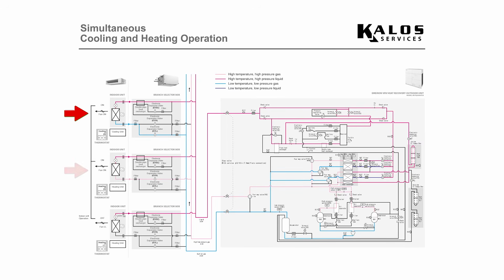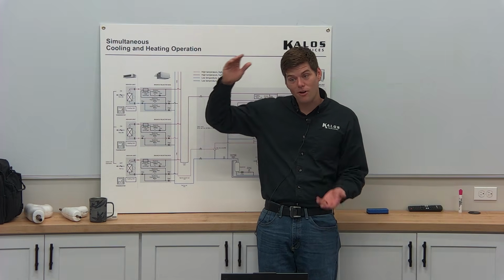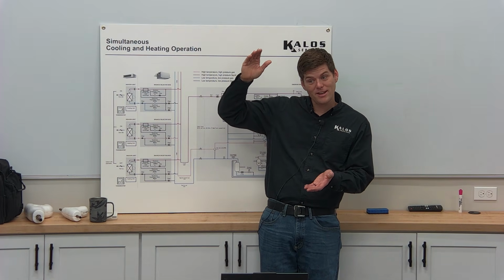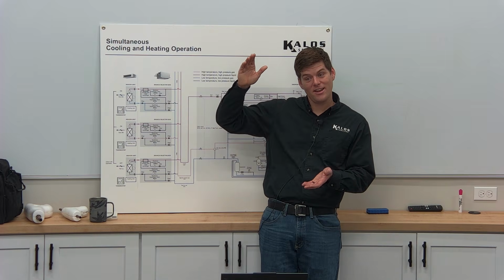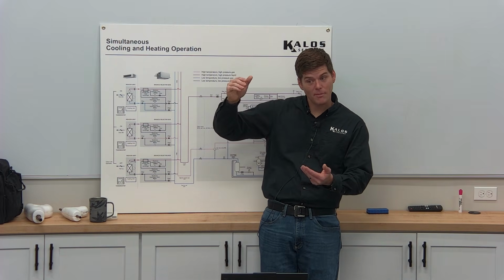So if we have 3 indoor units, right? 1, 2, 3. And this indoor unit's satisfied. We'll say this is, let's say room 101, right? But then room 102 says, I need to go into heating mode, right? I have a heating demand. The person's cranked it up to 80 degrees and it's 70 degrees in the space. They just came home. Unit turns on and it starts to deliver refrigerant to this specific unit, right? It's going to see how far off of set point something is and determine that unit needs a lot of capacity, right? Speed up. Deliver that capacity.